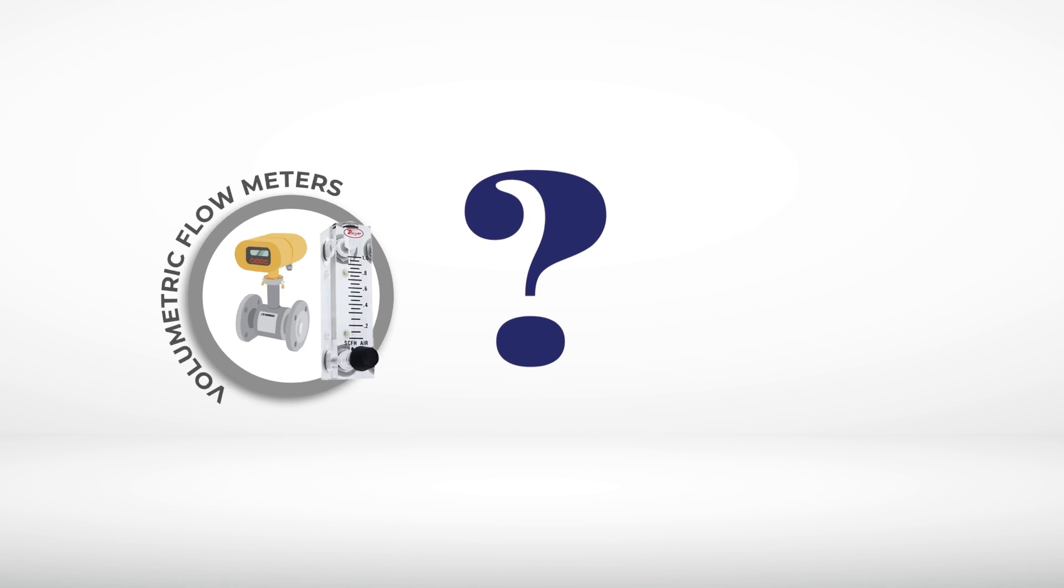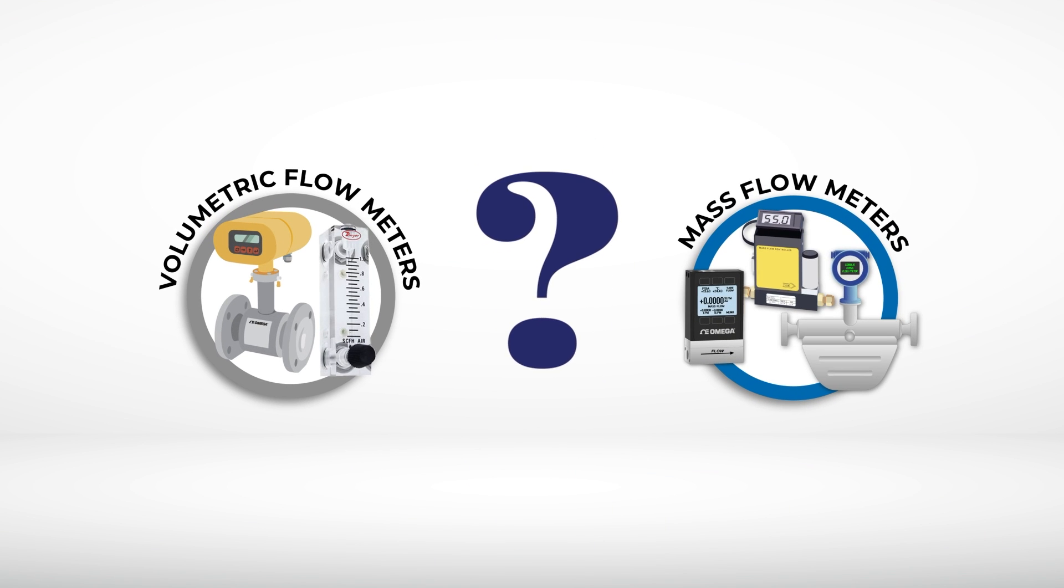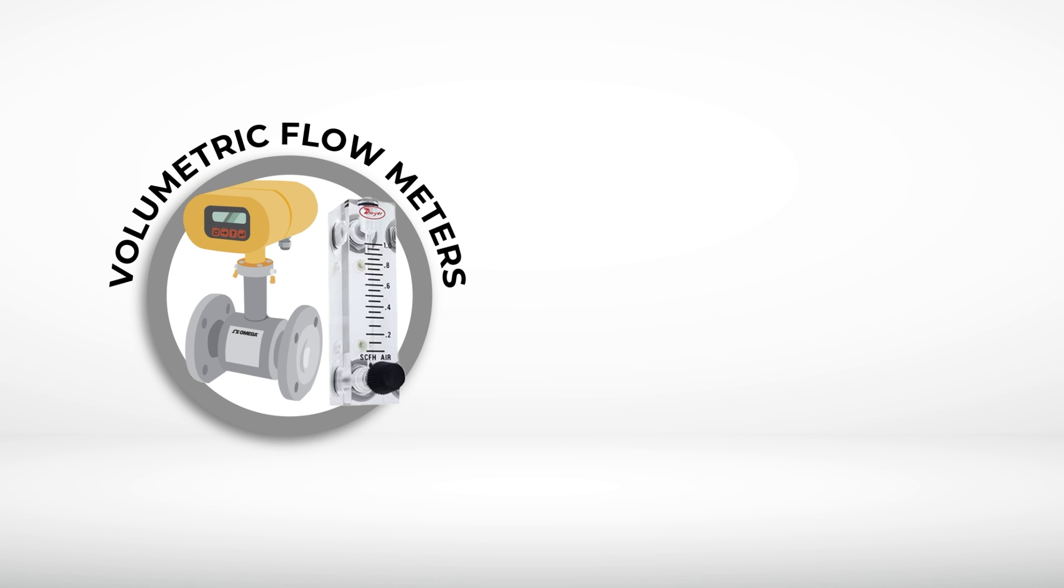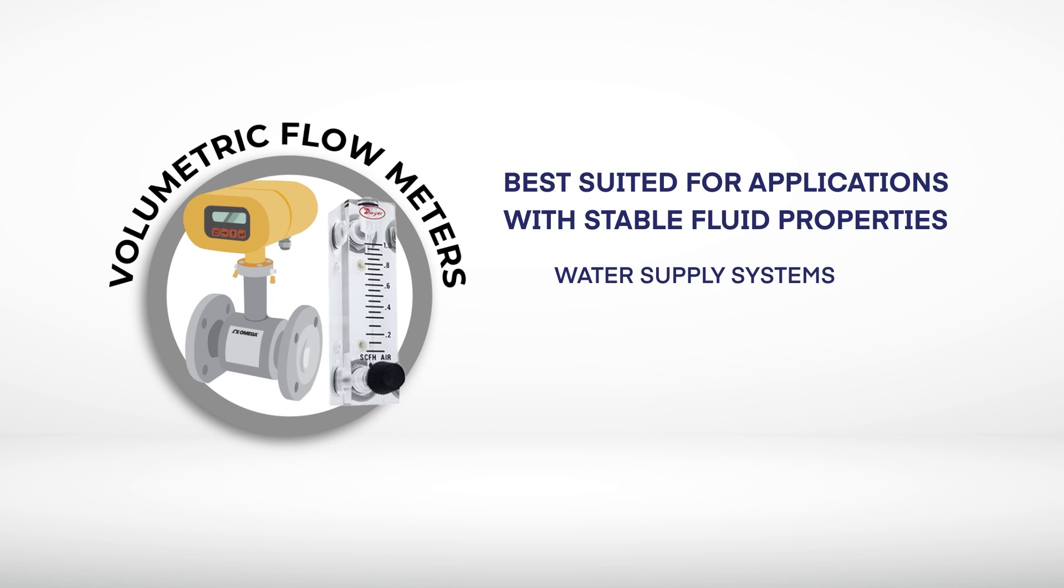Whether to use a volumetric flow meter or a mass flow meter depends on the specific requirements of the application and what kind of substance is being measured. Volumetric flow meters are best suited for applications where fluid properties like density, temperature, and pressure remain relatively stable. Applications such as water supply systems monitoring water consumption or measuring the flow of non-compressible fluids such as oils or chemicals, and in applications where very high accuracy isn't critical.